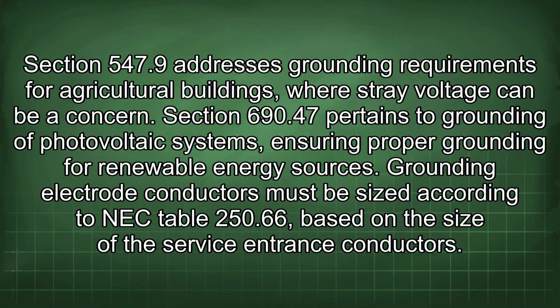Section 690.47 pertains to grounding of photovoltaic systems, ensuring proper grounding for renewable energy sources. Grounding electrode conductors must be sized according to NEC Table 250.66, based on the size of the service entrance conductors.